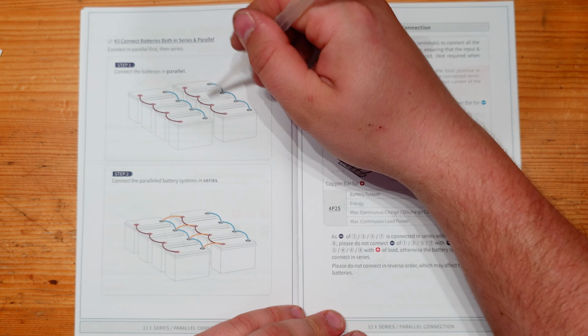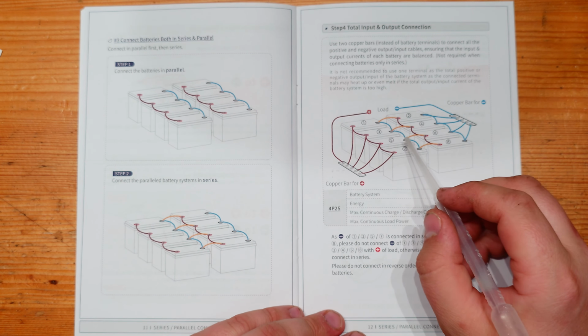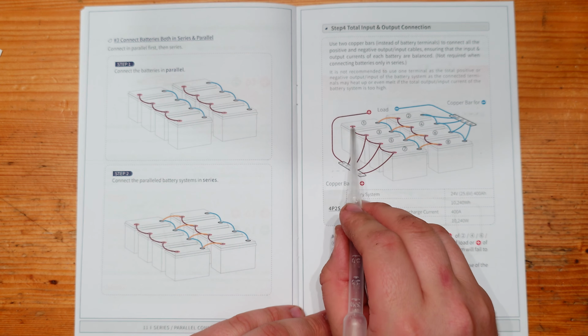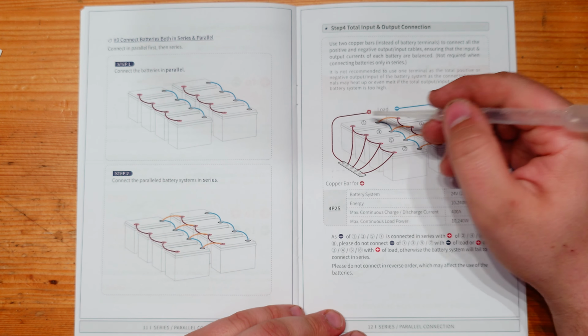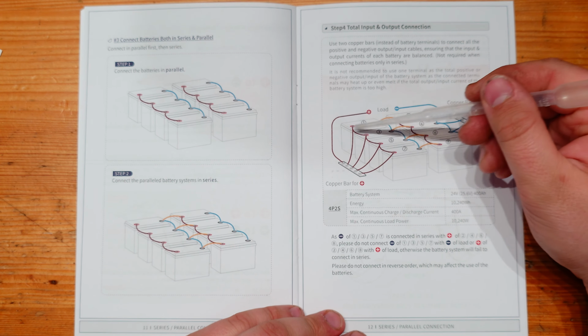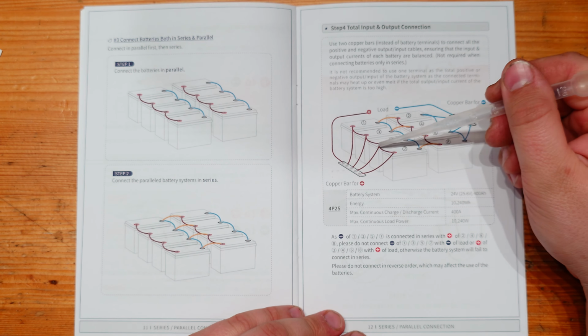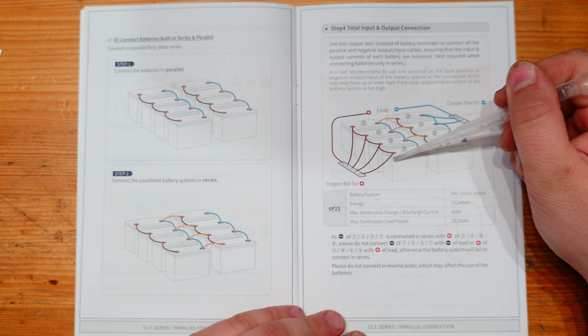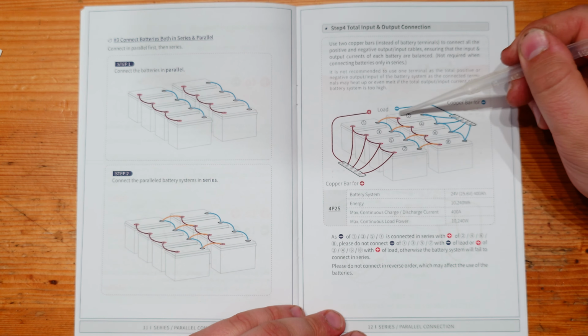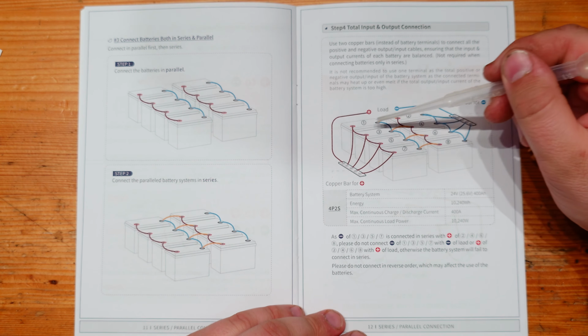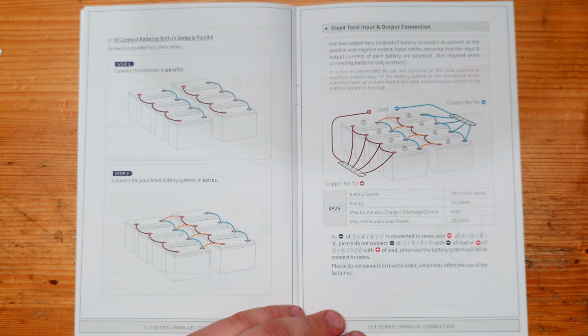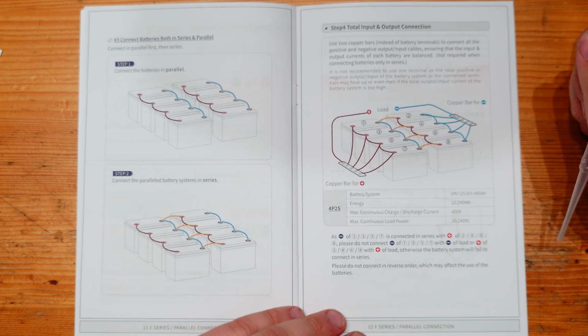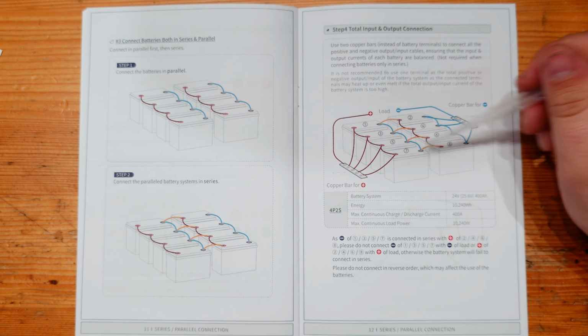If you would omit these balance interconnections, mainly these, then you would need just one fuse per most positive battery. So fuse on battery 1, battery 3, battery 5 and battery 7. Should you use these interconnections, then you would need a fuse on each battery in the system, which is 8 batteries in this case. So it's a bad idea to use these interconnections.